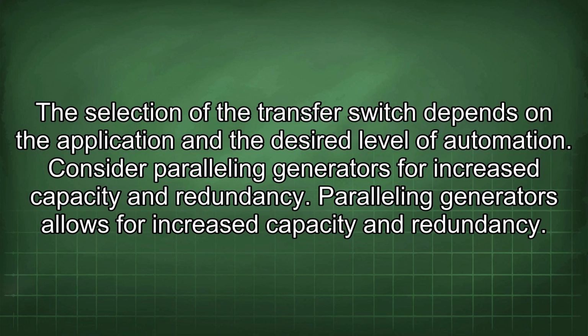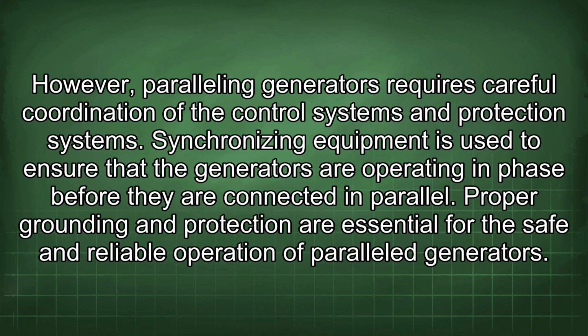Consider paralleling generators for increased capacity and redundancy. Paralleling generators allows for increased capacity and redundancy. However, paralleling generators requires careful coordination of the control systems and protection systems. Synchronizing equipment is used to ensure that the generators are operating in phase before they are connected in parallel. Proper grounding and protection are essential for the safe and reliable operation of parallel generators.